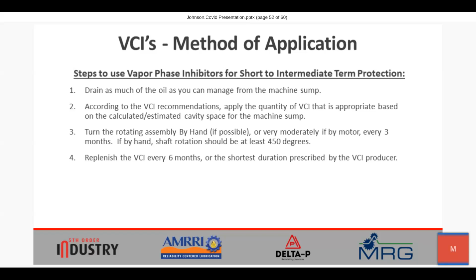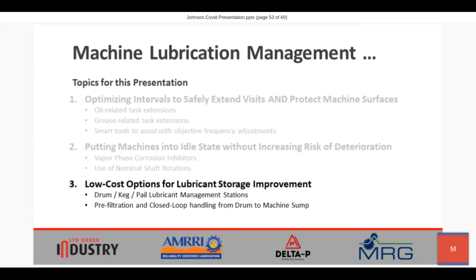And if we are able to turn it by hand, we should rotate it a full 450 degrees, and it should be done at no less than every 3 months while the machine is in an idle state. And then lastly, as I've said previously, we should plan to resupply the VCI about on a 6-month interval. I would encourage you not to go beyond 1 year, whichever kind of product that you choose to use. So that's a little bit of information about putting machines into either short-term or perhaps even long-term storage if it's needed during this period of manufacturing and productivity disruption.